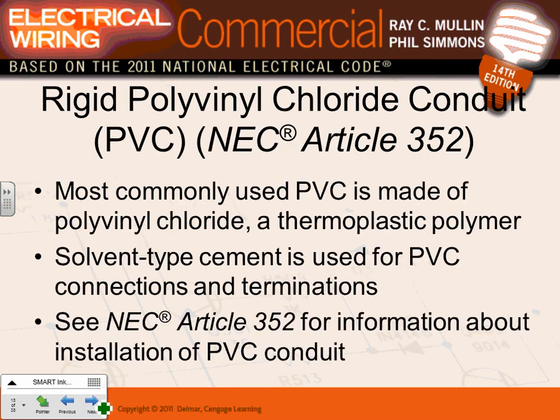PVC conduit - when would it be a good idea to use cables instead of conduits? A good example: take an EMT conduit three-quarters of an inch to a J-box, then use MC cable from the J-box to feed all the lights. If you have studs and sheetrock walls in a commercial building, MC cable is a great application - it's the cheapest and easiest method. The drawback of cable versus EMT: with cable you're stuck with what you have. With EMT conduit, you can add conductors later for future expansion.